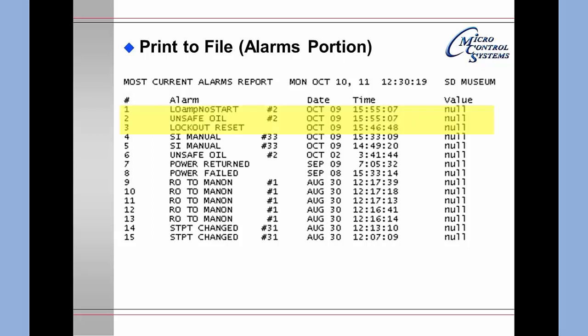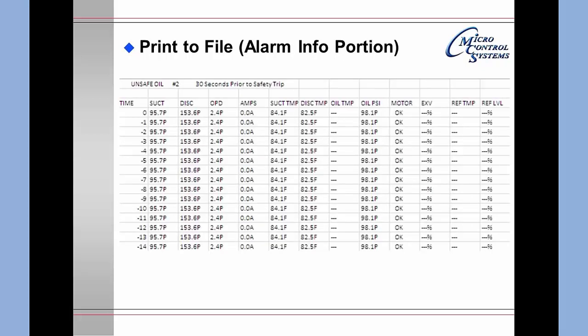The first alarm is the low amp no start, meaning we fired our relay but the compressor never started. At the same time there was an unsafe oil alarm, as the timing was exactly the same for both alarms, and then the unit had been locked out with a reset about eight minutes before. Going down to alarm number 6 you will see that an unsafe oil had occurred on circuit 2 about a week prior at about 3:41 in the morning. This is an information printout from an alarm, showing only the first 15 seconds of the available 30 seconds of data.